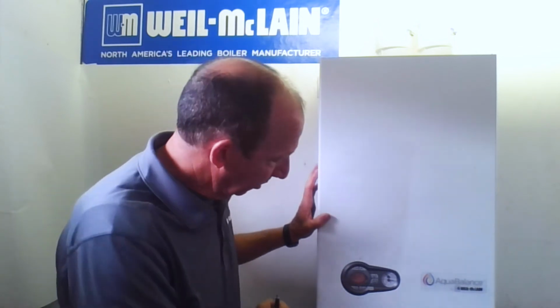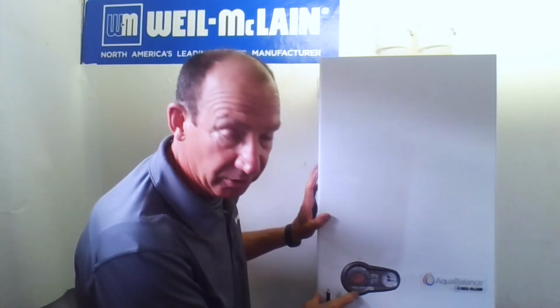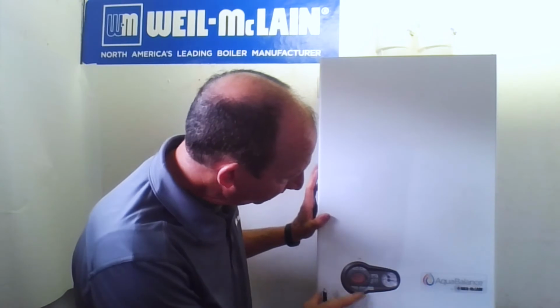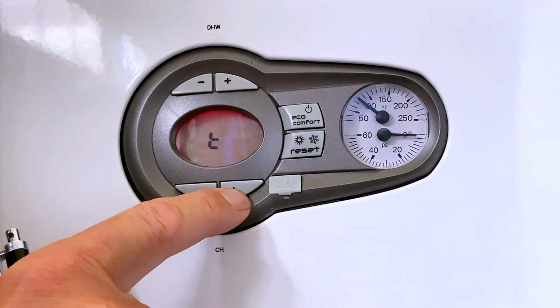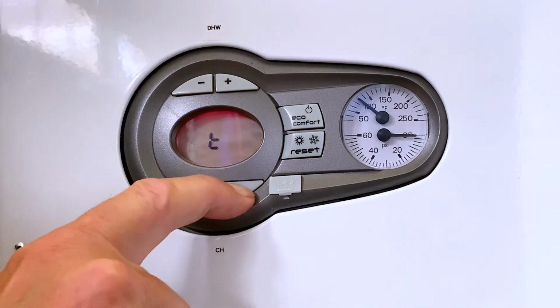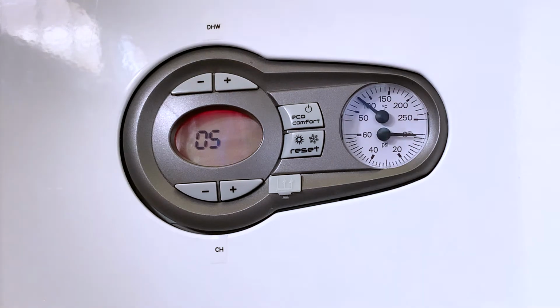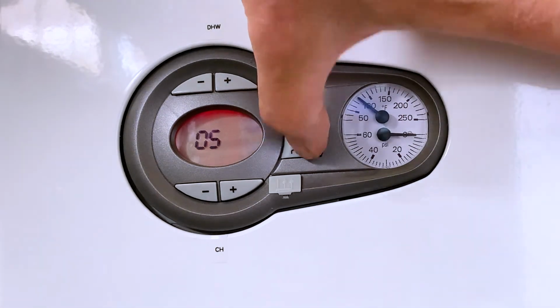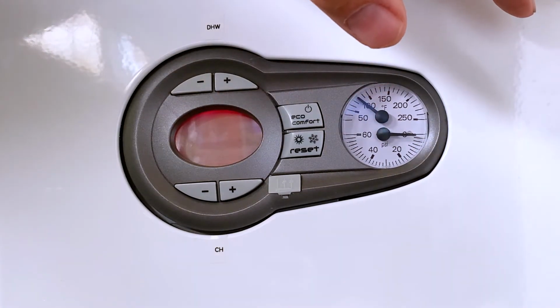If they get to a greater than 10 degree spread, then the boiler will give you an indication that you're having a temperature sensor issue. But as I move on to the next temperature sensing, you'll see that we can get all the way through those temperature values. So that's quite a nice feature. If I want to back out of there, it takes me next to the history mode. I could pop into history mode and read the history values and so forth.